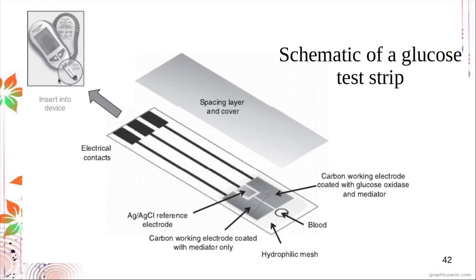Here is your glucose testing strip — the disposable test strip used with the reading device. You place blood at one end; the electrical contact connects to the device. The blood flows to the working electrode region. Because it is electrochemical, you have electrodes including a silver-silver chloride reference electrode for measuring the electrical signal produced. The strip is actually quite small and very thin.